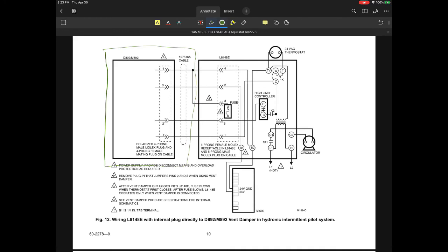is on a lot of the more efficient systems, where you would have, let's say, a vent damper that would be on a category 1 type boiler. What would happen then is the vent damper would be powered from the respective model of device that would say, I absolutely, 100%, have to power the vent damper and open this up 100% prior to ever allowing a burner to run. It has to open 100% before the burner will be allowed to run, before burner operation. And so this is more typical of a lot of those systems.